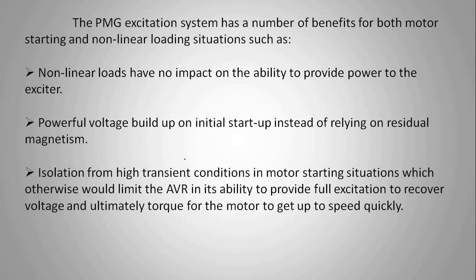Also, the alternator is isolated from the high transient conditions in motor starting situations, which would otherwise limit the AVR and its ability to provide full excitation to recover voltage and ultimately torque for the motor to get up to speed quickly.